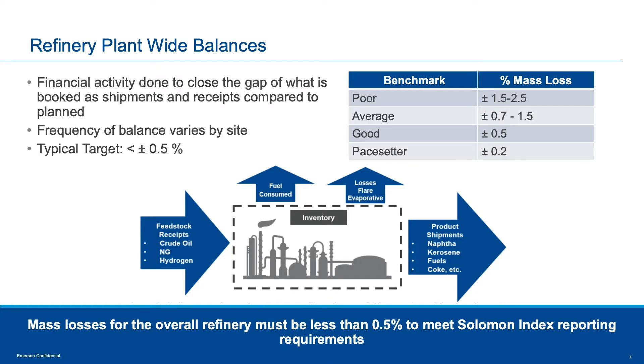This data is taken from Emerson, one of our key business partners. This slide gives the order of magnitude of a site-wide imbalance for an oil and gas refinery. In a typical refinery, the imbalance is about 2%, and the aim is to get it down to 0.2%. This translates to millions of dollars lost due to poor data quality. If we extend to metals and mining, the starting point might be 5% with a target of 1% imbalance. For power generation, the starting point is about 1%, with the aim always being 0.2%.